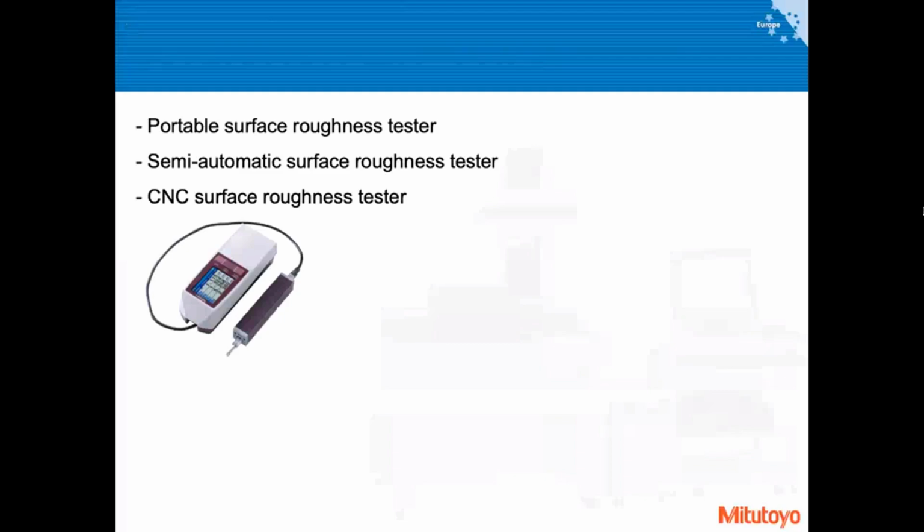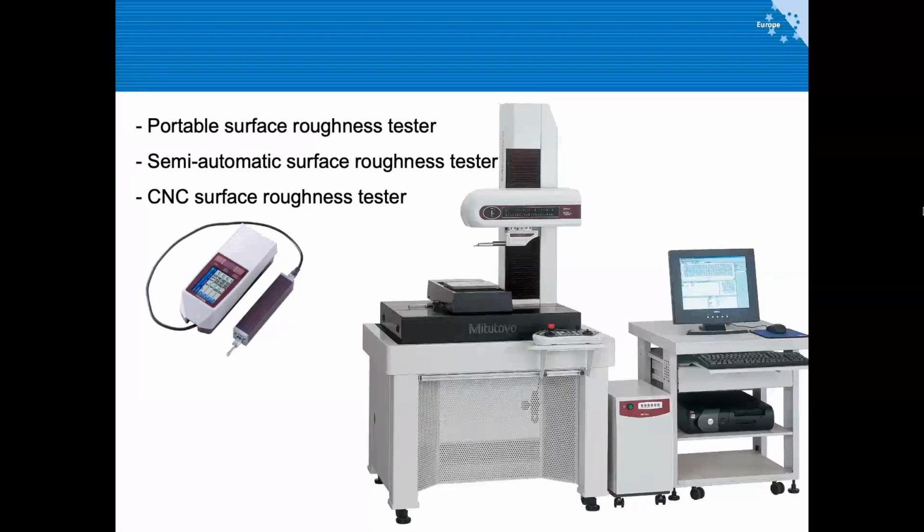So, how do you deal with the measurement problems? You purchase one or another type of measurement tool, and they can be portable, very simple, and fairly cheap. Typically it costs around 1.5 to 3,000 euros per unit if you want something like this. But if you want to go for something more advanced like here, then the price typically grows up to tens or sometimes hundreds of thousands of euros.